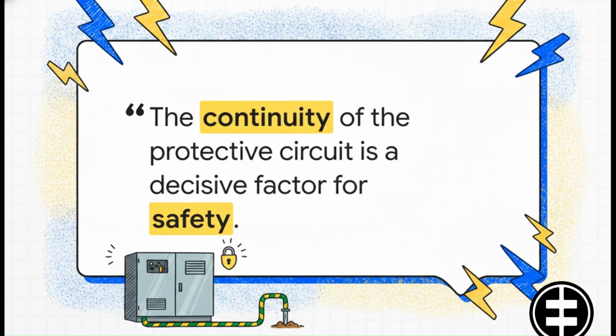The whole testing philosophy here dictates one absolutely crucial rule. The continuity of the protective circuit is a decisive factor for safety. Basically, no matter the electrical violence experienced during a short circuit, overall safety hinges entirely on this protective grounding circuit holding together. If it fails, well, the entire metal enclosure could become lethally electrified.